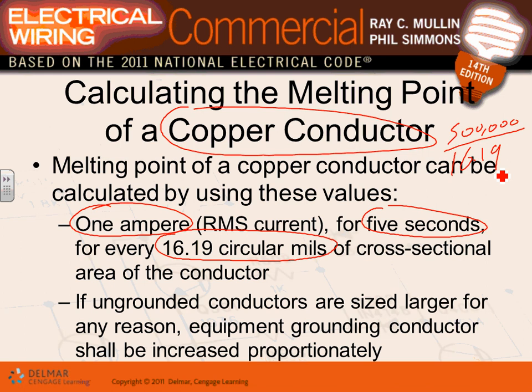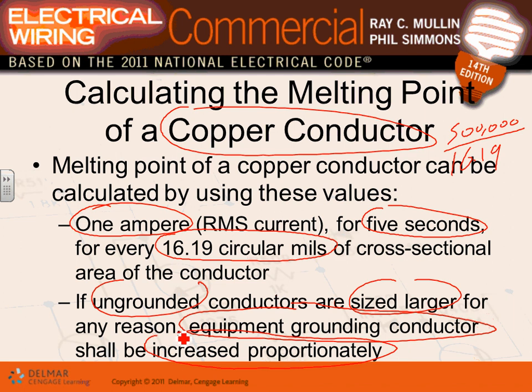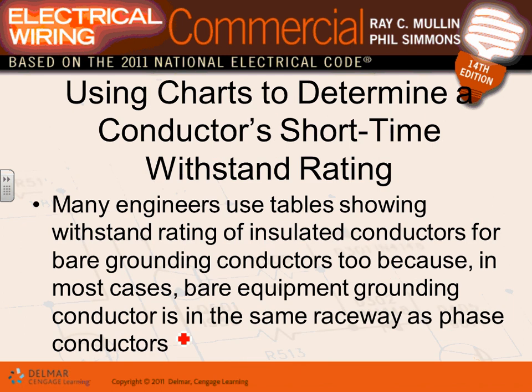What they're telling you, guys, for equipment grounding conductors: if you oversize the ungrounded conductor, size it larger, then you have to proportionally increase the ground conductor. Because if you oversize the ungrounded conductor, you will allow more current to go through during a short circuit condition. Then your ground fault conductors have to be proportionally upgraded, otherwise you will burn your conductors. And that's with your short circuit.